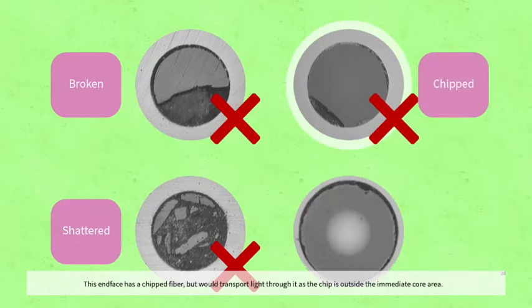This end face has a chipped fiber but would transport light through it, as the chip is outside the immediate core area. It is polished cleanly, and a poor cleave is the most likely cause.